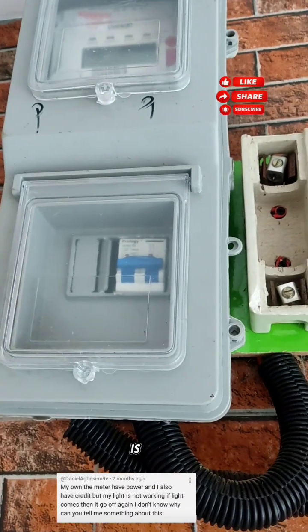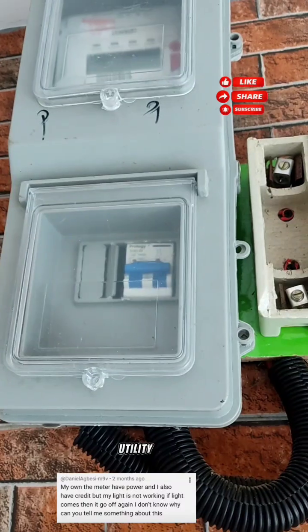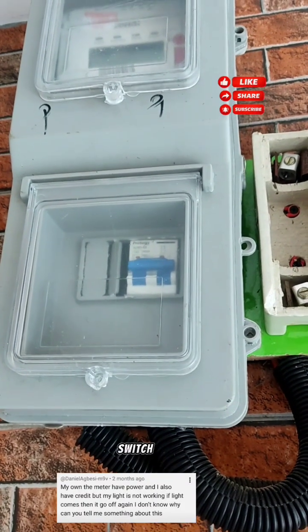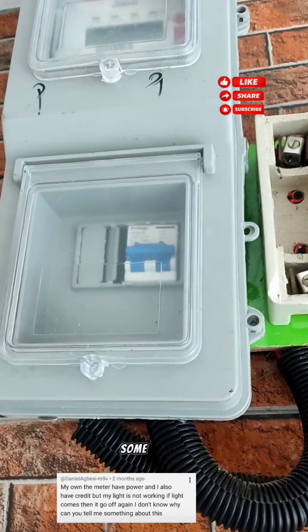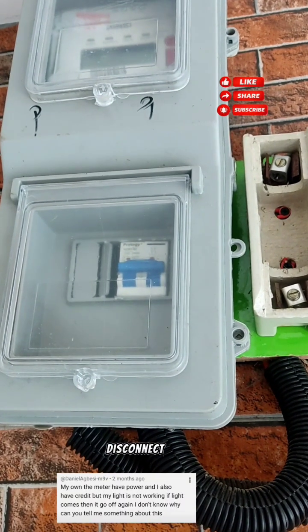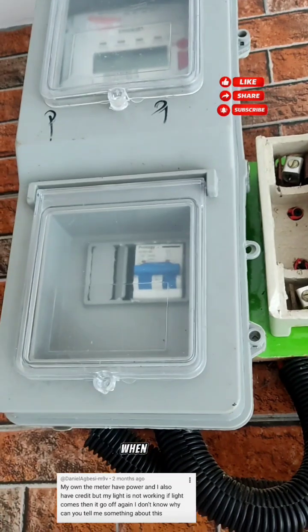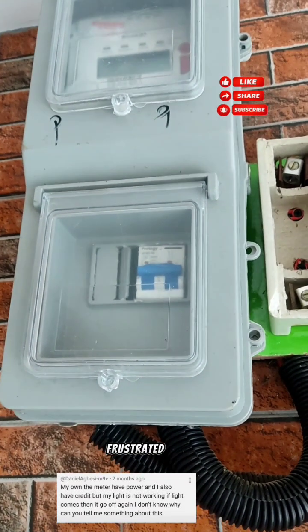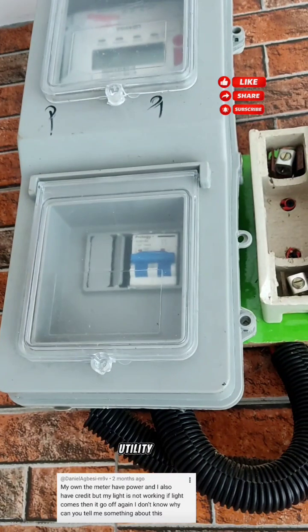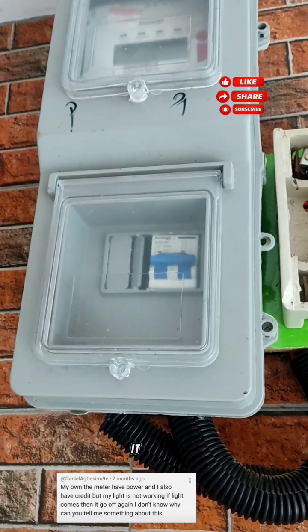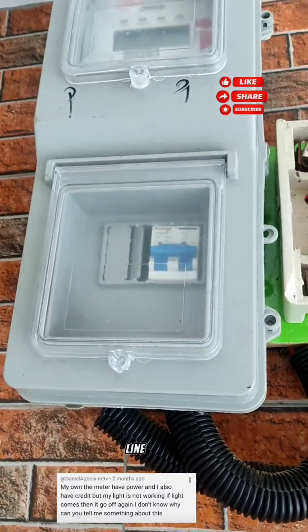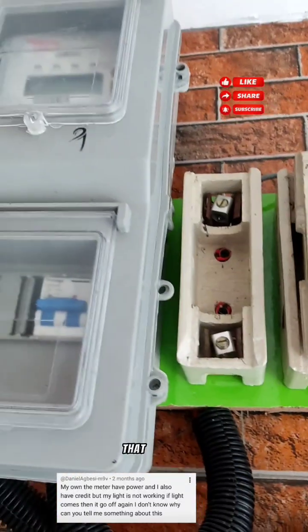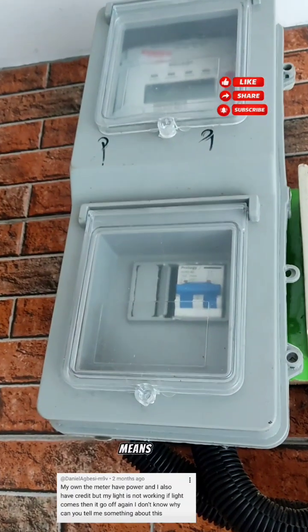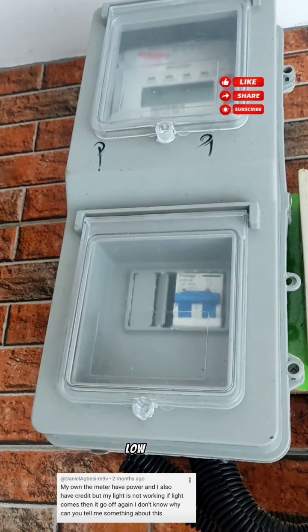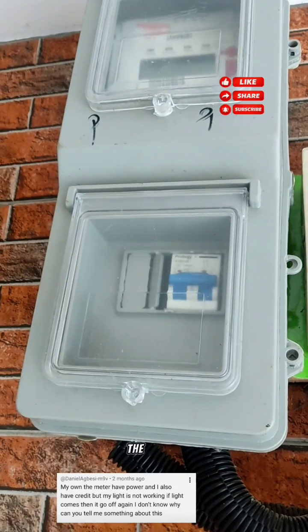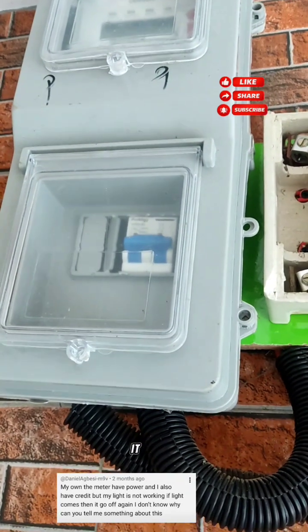Then the fourth reason is low or unstable voltage from the utility. Yes, if the incoming voltage fluctuates badly, some meters or protected devices may disconnect temporarily. When your meter detects fluctuating voltage coming from the utility, this will happen. It has happened in my own meter. And how did I solve it? I had to change the line. I had to change it to another phase. That is how I was able to solve that problem. It means that the voltage coming into your meter is too low, and when that happens, it tries to make up for the shortfall of the current that is coming, and it will trip off.